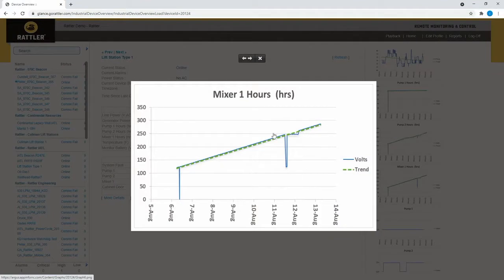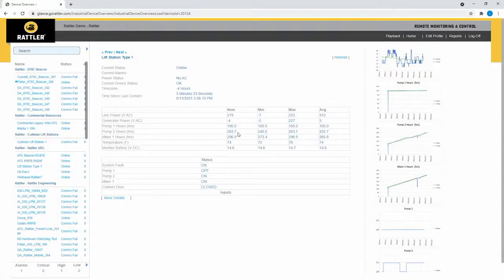This is actually when the hour meter was reset. There's a way of resetting it to the correct information that's on the mechanical hour meter out in the field. But if somebody looks at this every day and looks at the hours over here, they don't have to travel to the field. They can see the hour meter running on the user interface. The minimum and the maximum tell you how many hours the pump has run in the last 24 hours.